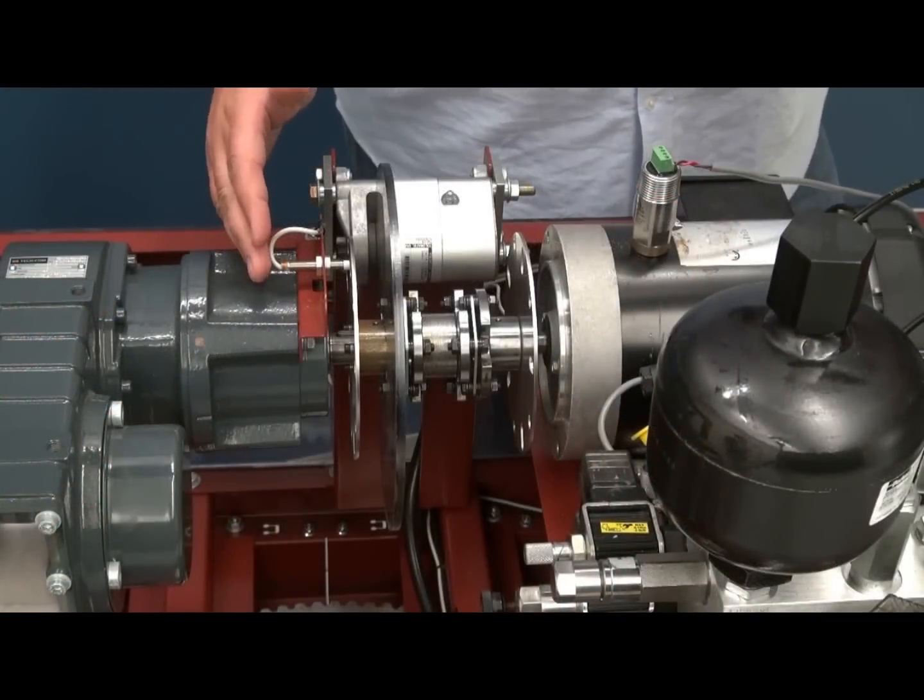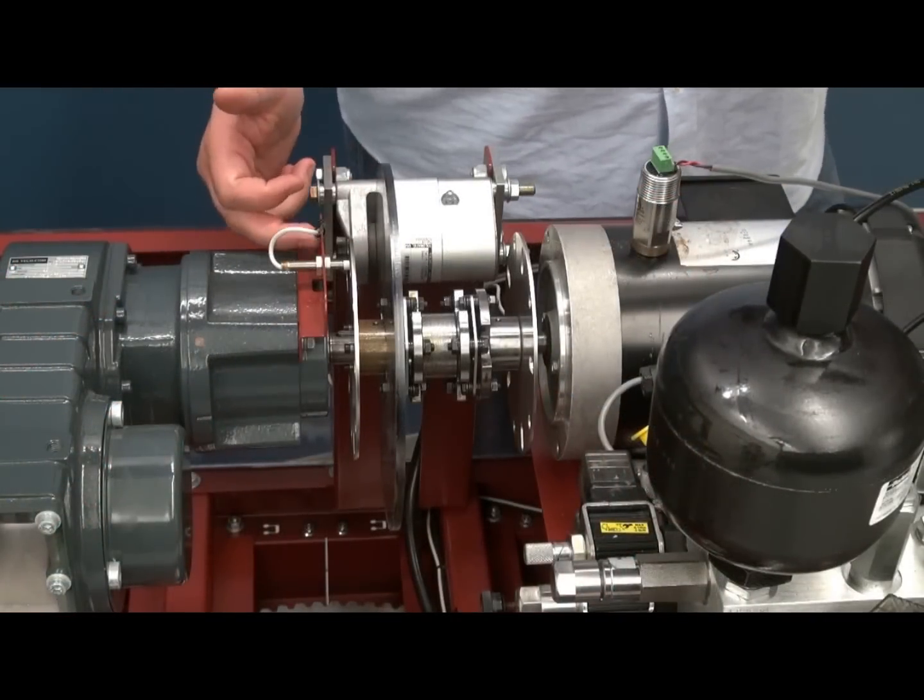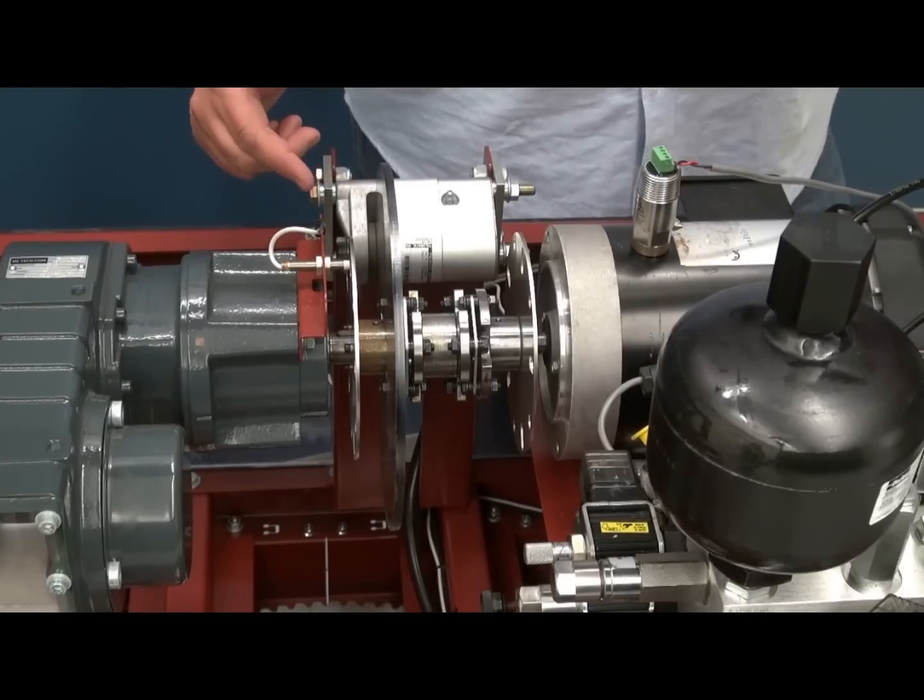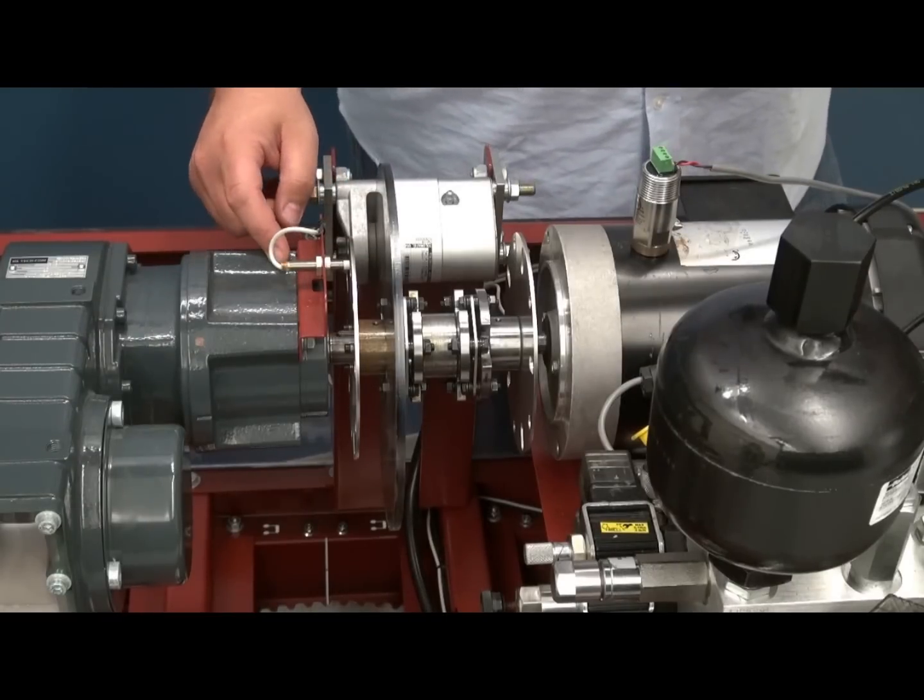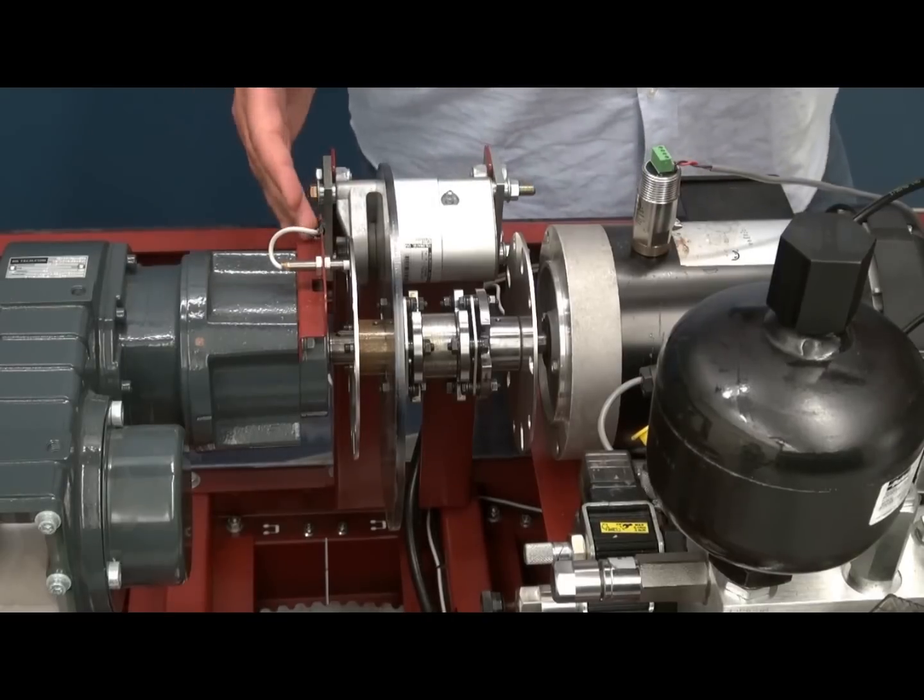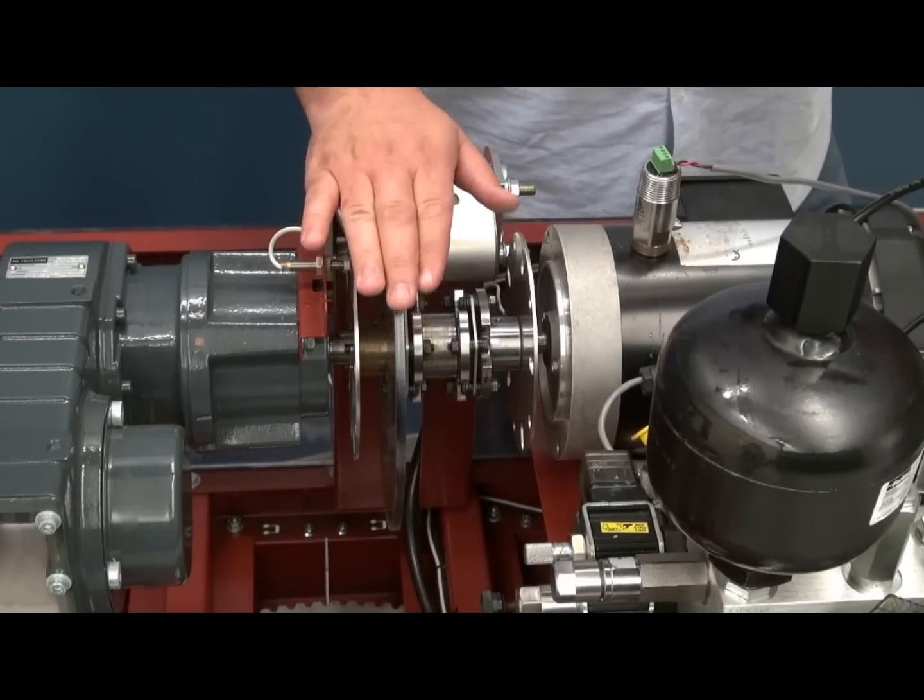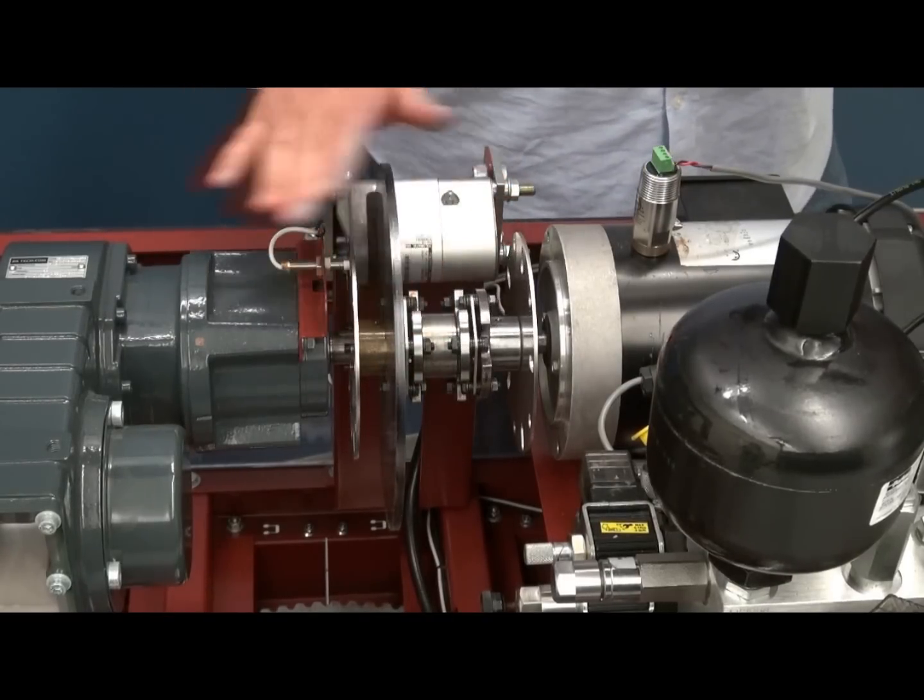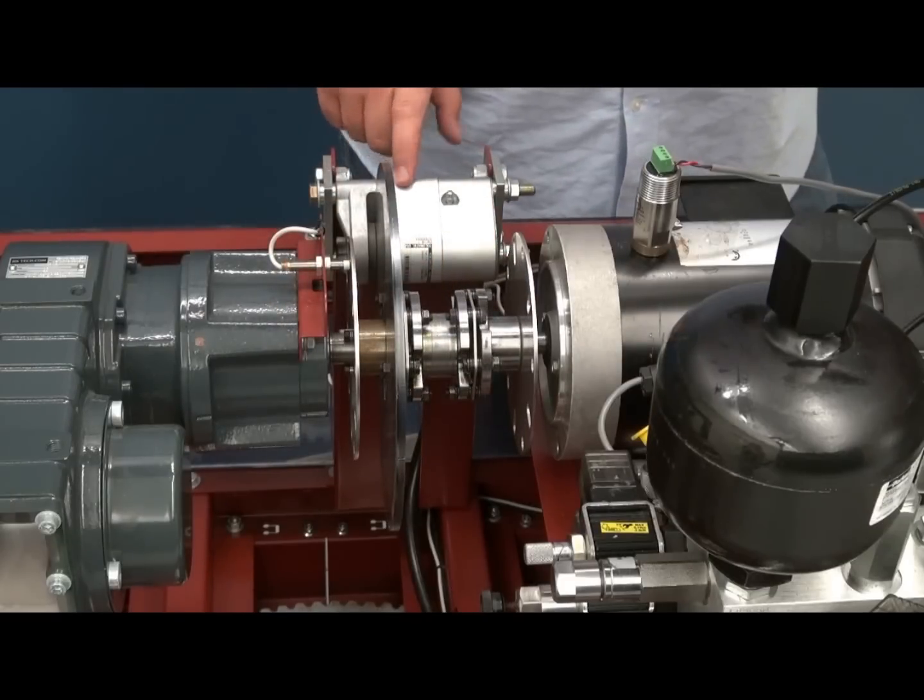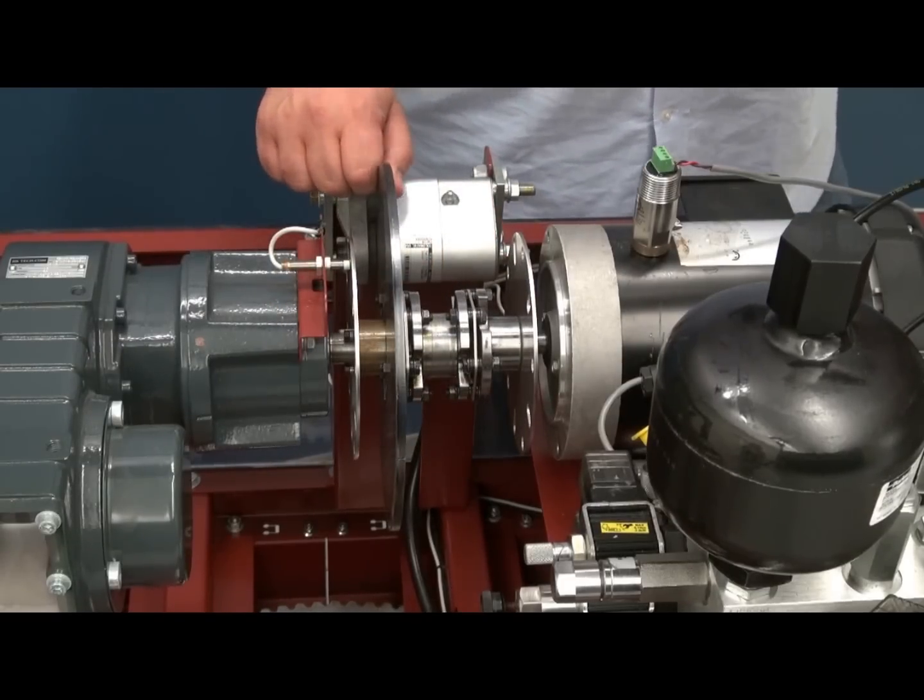When we exit the gearbox, the first thing we do is to measure the actual speed on the high speed side of the drivetrain with an inductive proximity switch. Then we have the main part between the gearbox and the generator, which is the disc brake, and then we have a double acting hydraulic brake that will break the disc and then break the whole drivetrain in case of emergencies or maintenance to be performed by a technician.